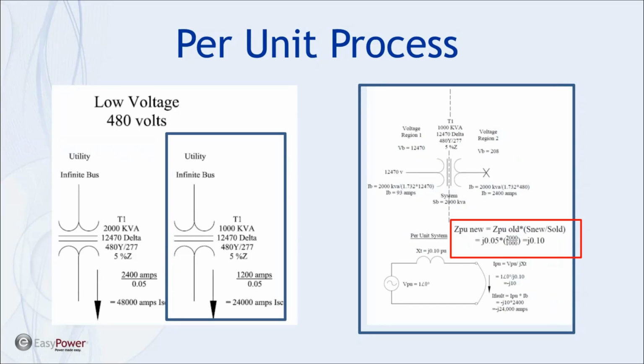What I'd like to do next then is add 1,000 kVA. Let's take our 1,000 kVA transformer and put it into a per unit system where we use a base system with an S base of 2,000 kVA. When you do that, we have to do this change of base calculation, where we take the original impedance of the transformer, which was J.05, and this is something that you might do if these transformers were going to be connected radially, and you were going to do per unit calculations with them. If these were both tied to the same bus and we wanted to put them into the same per unit system, and we were going to establish S base as 2,000 kVA, we'd have to do the change of base on the percent impedance here.